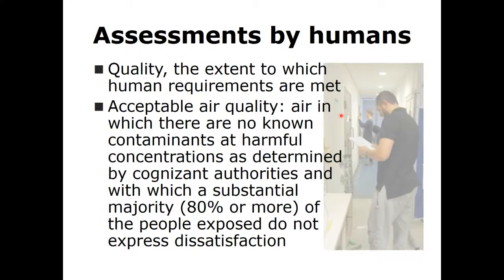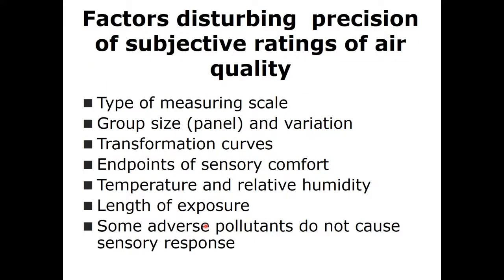And then we have assessment by humans. Basically we can ask people to evaluate air quality by the extent to which human requirements are met. So it is in the standards: European standard EN 16798 and ASHRAE standard 62, where the prescriptive numbers are based on this type of evaluation. And basically they define the level of dissatisfaction caused by air quality, by people assessing the air entering the space. However, there are several factors that disturb the precision of those ratings. And again, this is not a very solid metric, because it depends on the type of measuring scale, group size, and different methods of transferring the responses to some dissatisfaction level. Temperature and relative humidity are very important parameters that will interfere with those measurements. And there are also some adverse pollutants that do not cause sensory response and are not addressed in this.